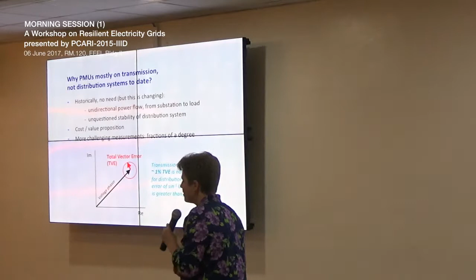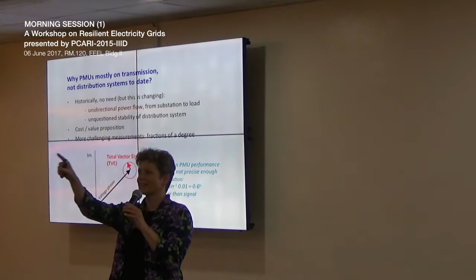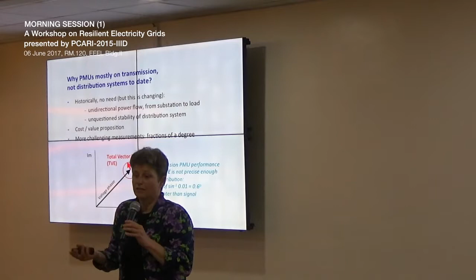The performance of transmission PMUs is conventionally described in terms of a total vector error, which is basically, in the complex plane, the radius of that red circle—if you measure the voltage phasor, you're going to get it to within some distance. It could be a magnitude error, a phase angle error, or a time error. So in transmission, if your PMU is within 1%, or 0.01 per unit of the magnitude of that whole phasor, then you're okay—you're meeting the standards and expectations.